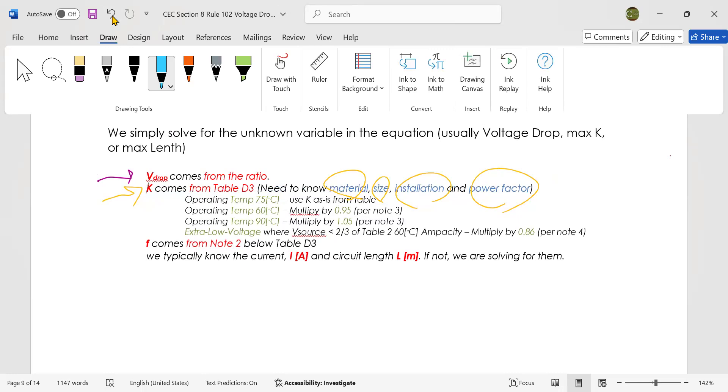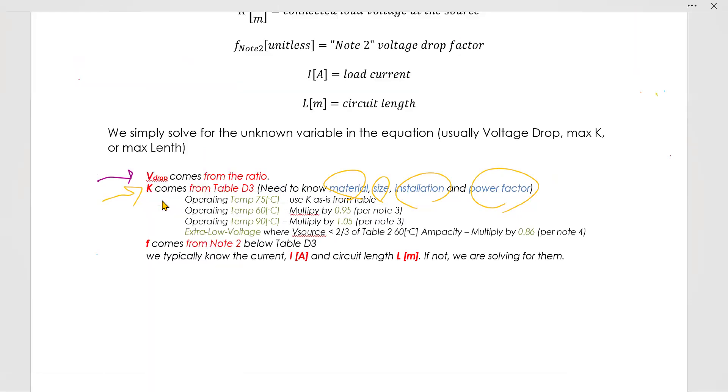We use it just as it is from the table if it is 75 degrees. Take it from the table. But if the operating temperature is lower than that, then we can make the K value a little bit higher. We multiply by 0.95. That's shown in note 3. If the operating temperature is higher than that, you're going to multiply by this - factor 1.05.